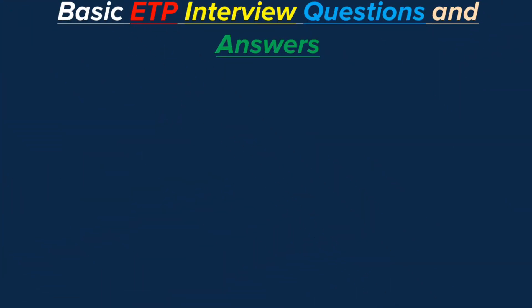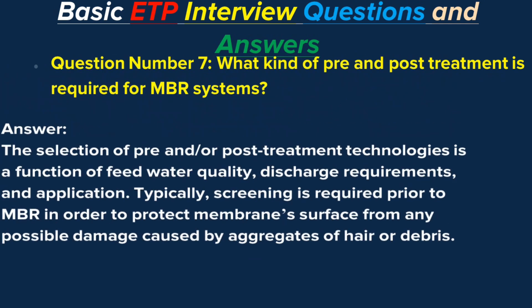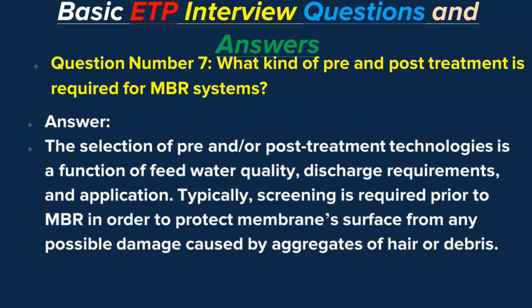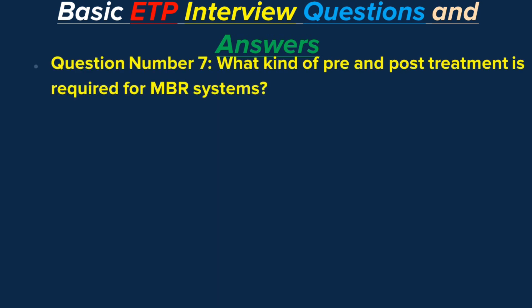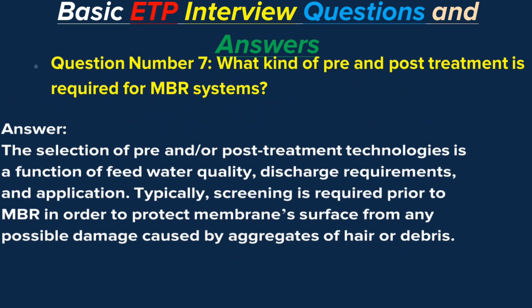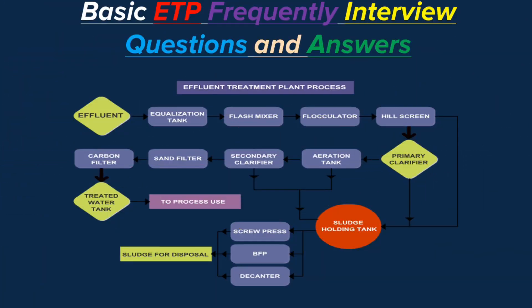Question number 7: What kind of pre- and post-treatment is required for MBR systems? Answer. The selection of pre- and/or post-treatment technologies is a function of feed water quality, discharge requirements, and application. Typically, screening is required prior to MBR in order to protect the membrane surface from any possible damage caused by aggregates of hair or debris.